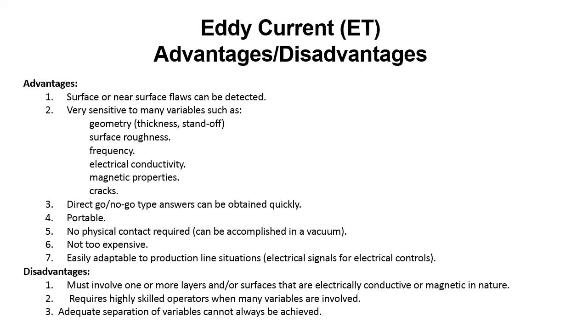Eddy Current Testing Advantages and Disadvantages. Advantages: surface or near surface flaws can be detected. Very sensitive to many variables, such as geometry, surface roughness, frequency, electrical conductivity, magnetic properties, and cracks. Direct go/no-go type answers can be obtained quickly. It's portable, no physical contact required, can be accomplished in a vacuum. Not too expensive, easily adaptable to production line situations. Electrical signals for electrical controls. Disadvantages: must involve one or more layers and/or surfaces that are electrically conductive or magnetic in nature. Requires highly skilled operators when many variables are involved. An adequate separation of variables cannot always be achieved.